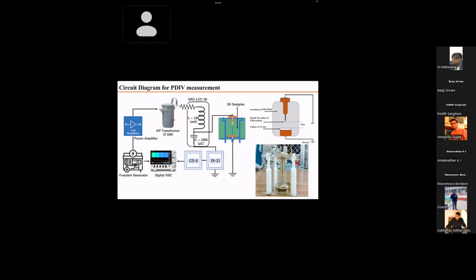In the case of a normal power transformer or high voltage transformer, the design stress in mineral oil would be around 1 kV per mm, am I right? So what would the design stress be in ester oil? Because in mineral oil, there is a significant permittivity difference between kraft paper and the oil. For example, mineral oil has permittivity of 2.2, whereas ester oil has around 3.2-3.3. So ideally the ester oil would be stressed a little more than mineral oil.